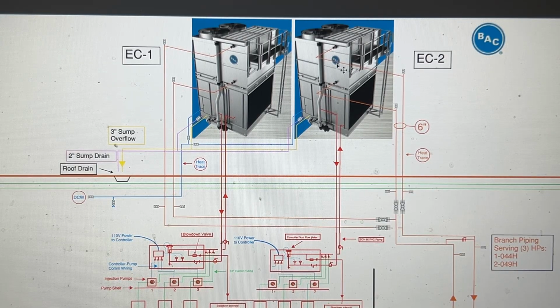So as they spray down, these fans here up top are drawing in air and pulling it up and across. So it is a counterflow unit. And basically what that does is spraying that water onto it is going to get the heat removed required to cool that water down. So in cooling season, we utilize the cooling towers. In heating season, these cooling towers get shut down, the sumps get drained out, these two units get winterized, and then they're relying on, in the basement of the sub-basement, heat exchangers, which are steam-driven heat exchangers, which they'll use the steam as the heating property to heat the heat pump water.